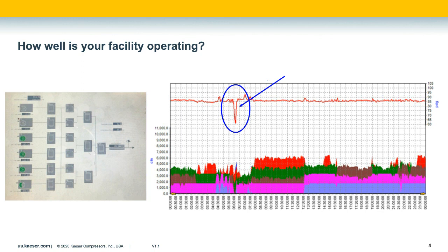Same example as I used previously with a severe pressure drop in the plant, but here you can actually see that graphically. Pressure's fallen. And if you look a little bit closely, and like Travis said, I've looked at a lot of design audits, so this stuff is intuitive to me, but maybe not to you folks out there. But you can see there's actually about 5 different colors of compressors that are running on this particular sample day.